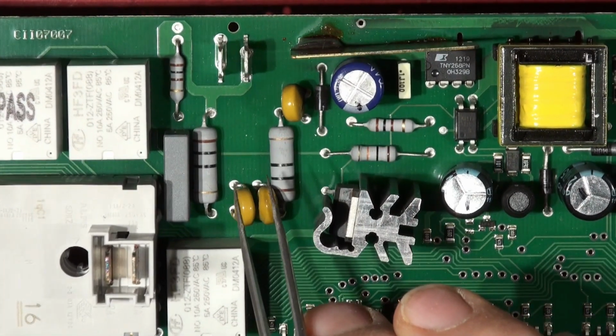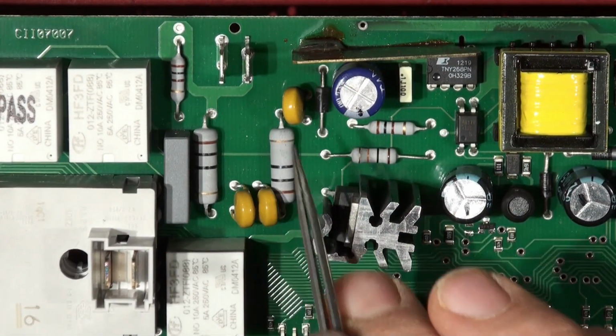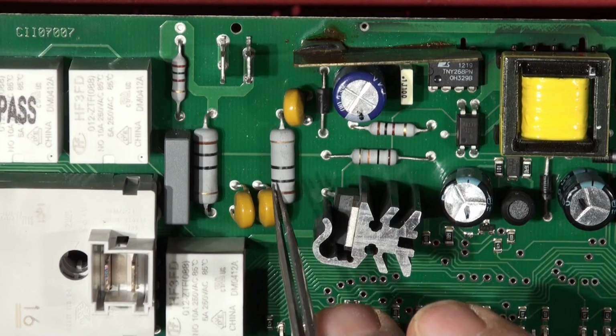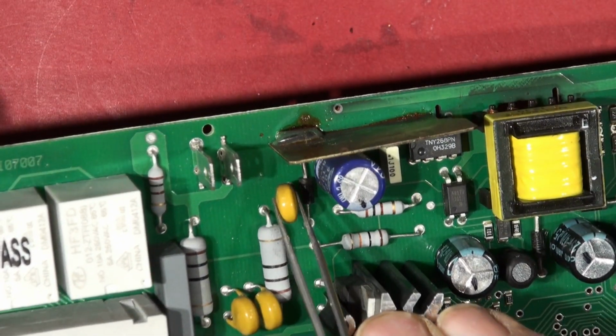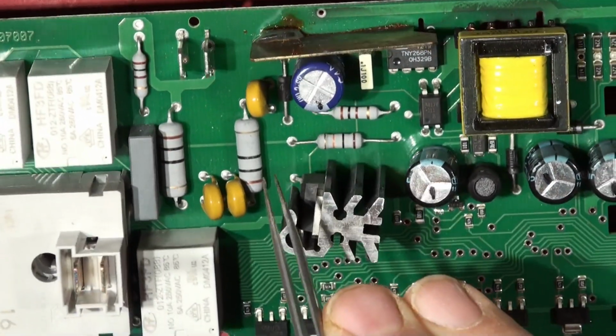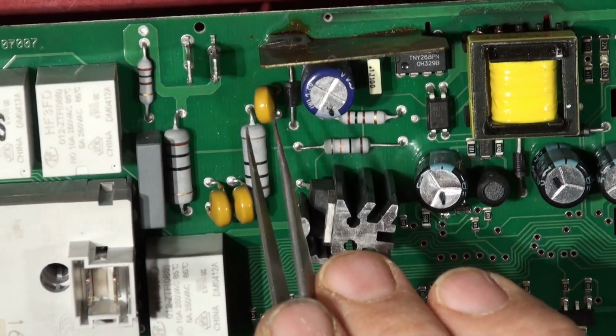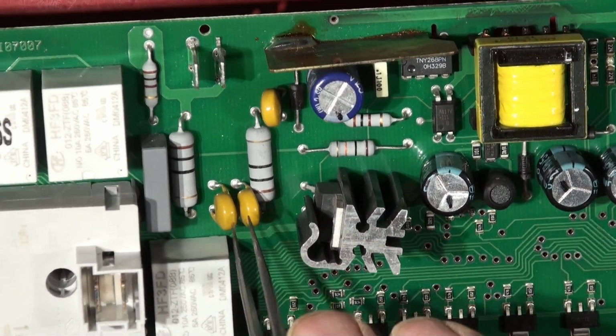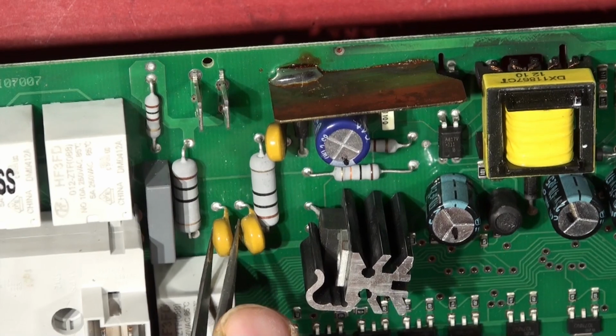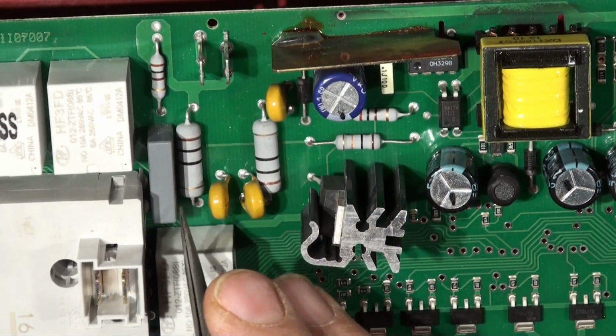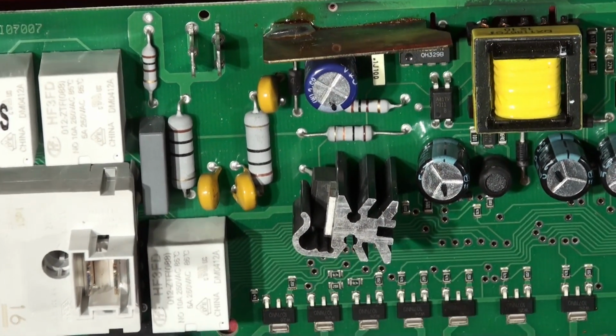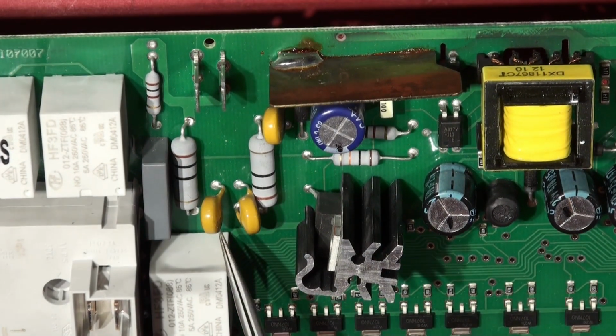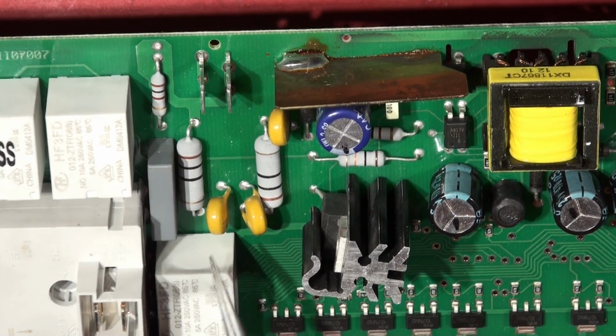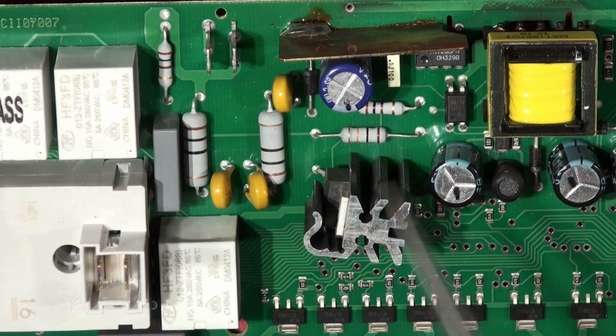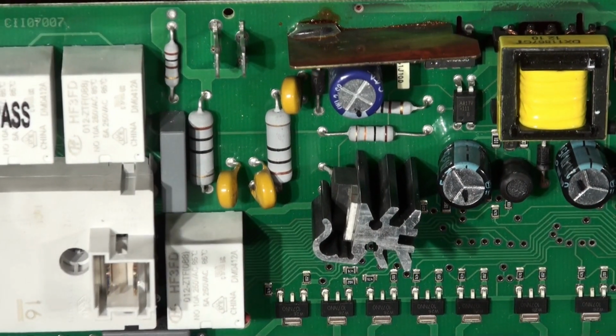It's got no common mode choke. I'm not sure if that's a thermistor or what that is - it's probably to limit the inrush current. It's probably a thermistor, or it might be a varistor, an overvoltage varistor to soak up any mains transients that come down. Yeah, they are. So there is some protection, but not much of anything else.